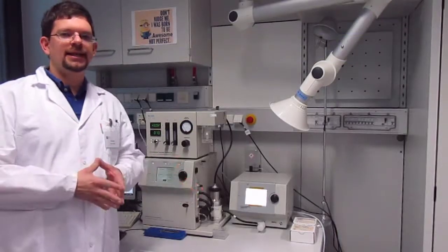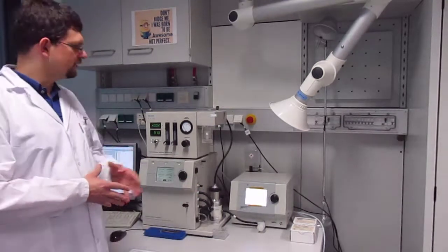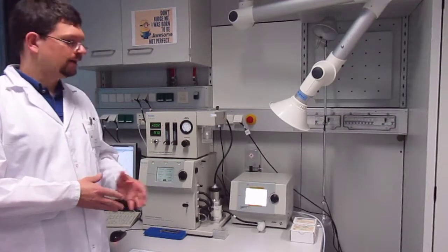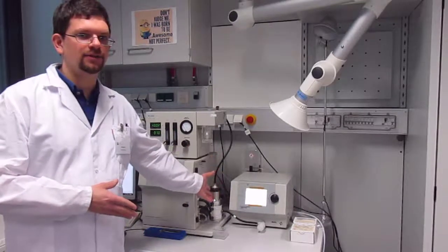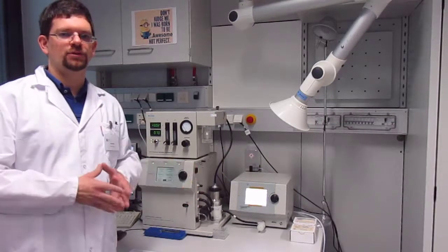This is the nES GEMMA instrumentation as it can be found in our laboratory. It consists of the nanoelectrospray source with a charge reduction device, the electrostatic classifier with the nano-differential mobility analyzer at its site, and the condensation particle counter as the detector unit of the instrument.